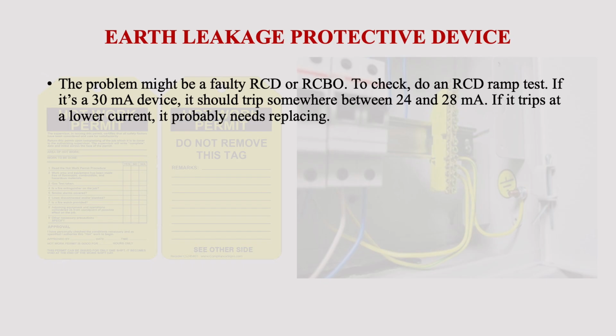Suppose the milliampere rating of the earth leakage protecting device, whether it is an RCD or RCBO, is 30 milliamperes, which is the most common rating. Then it should trip somewhere between 24 and 28 milliamperes when current flows through it. If it trips at a lower current, it probably needs replacement.